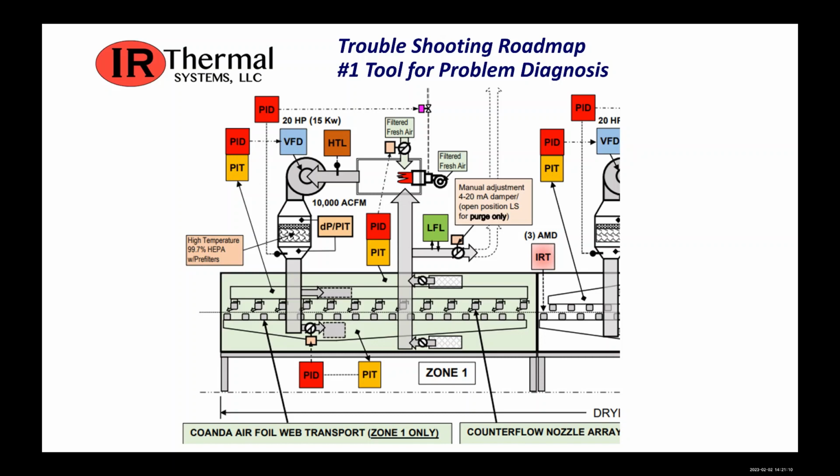If we were to install an inline heater and raise that 60-degree air up to 160 degrees, that 240-degree delta across their heat source would no longer go from 60 to 300. They'd go from 160 to upper 300s, maybe 400 degrees. So that seems like the process that we're going to go through there. And once again, the P&ID was a pretty simple one, but the P&ID gave us all the variables that we were allowed to work with.